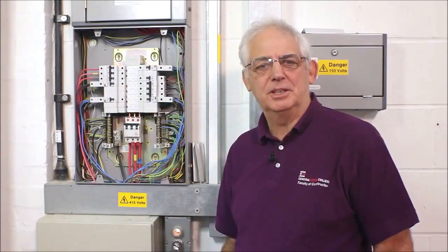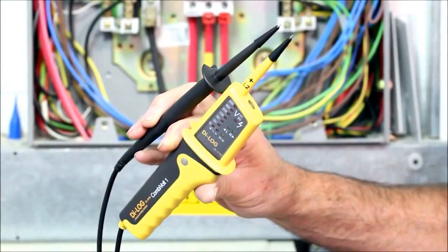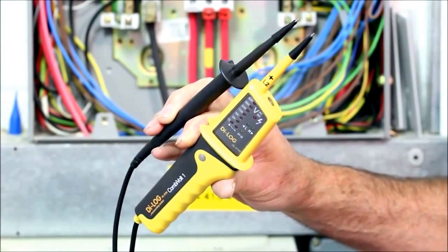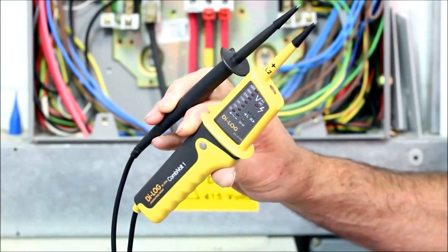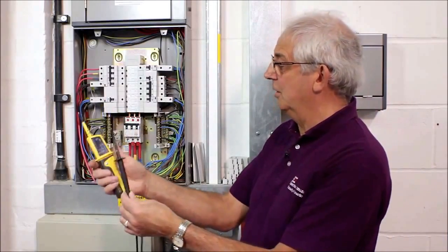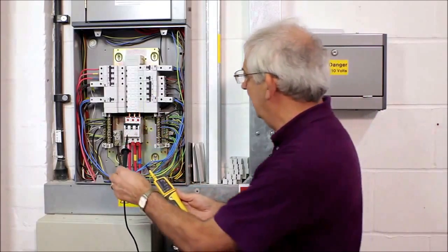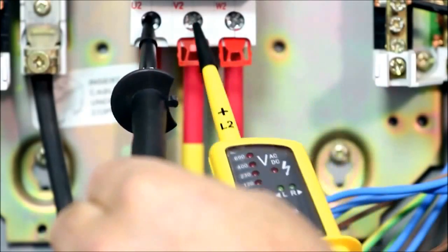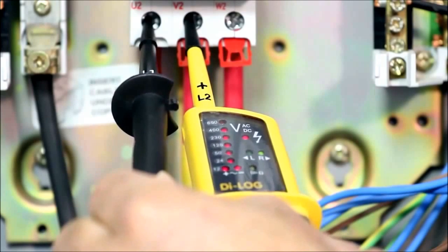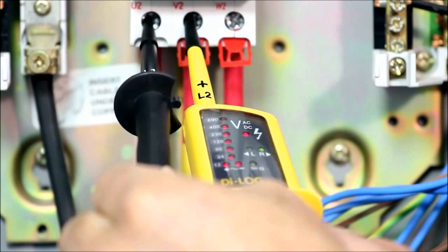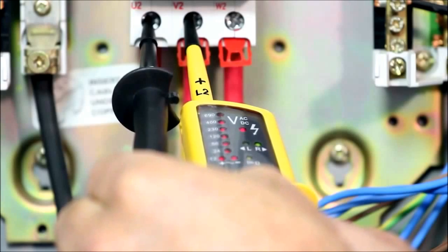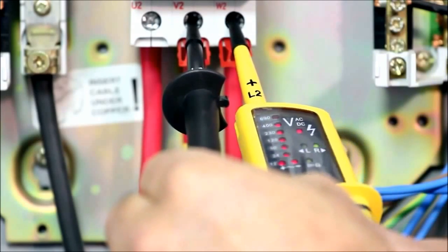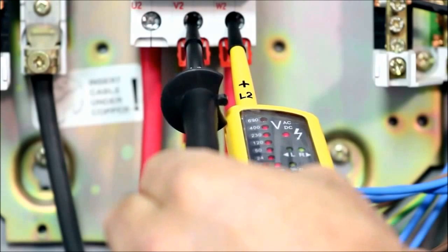Another way of measuring phase sequence or phase rotation is to use an approved voltage indicator, which has got the facility for phase rotation on it. This is a particularly good one, and all I need to do really is, these are indicated L1, L2, okay? So if I put L1 on line 1 and L2 on line 2, you can see that there's a green light against the R on the right-hand side of the indicator. Okay, that tells me that the rotation is correct.